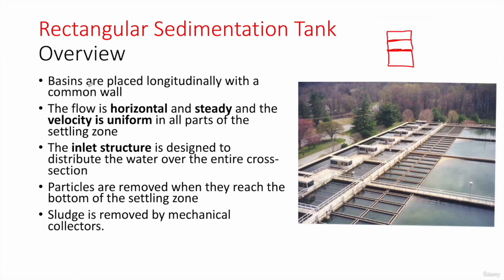These basins are placed longitudinally with a common wall. The flow is horizontal — a steady, uniform flow with minimal disturbance. Our aim is to have laminar flow throughout the settling zone. We have an inlet structure to distribute the water over the entire cross section. Particles are removed when they reach the bottom, the sludge is removed by rotating mechanical scrapers, and the clean water is collected through launders.